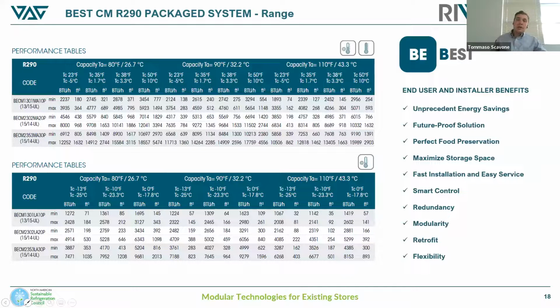propane per circuit. As standard conditions, with the larger models, we achieve about 15,000 BTUs in medium temp and 9,000 BTUs in low temperature. Plus, I would like to remind you that these monoblocks have a controller, or are provided with a master controller that allows you to control up to 5 other auxiliary units on the same walk-in. So from a single display, you can have a total of 6 units on the same walk-in controlled by a single display. This product is going through UL certifications next month, NSF on the evaporators, and everything will be approved by the end of this year. First prototypes or pre-series will be launched on the market by February 2023, and mass production will take place in March.